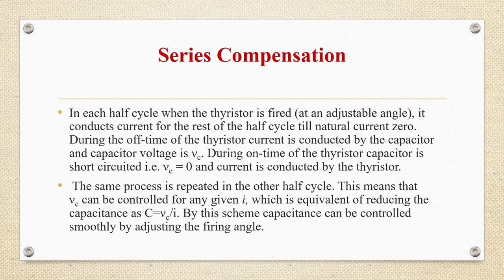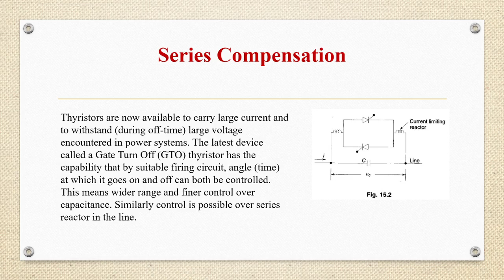Thyristors are now available to carry large current and to withstand the large voltage encountered in power systems. The latest device, called the gate turn-off thyristor (GTO), has the capability that by a suitable firing circuit, the angle at which it goes on and off can both be controlled. This means wider range and finer control over capacitance. Similarly, control is possible over a series reactor in the line. All the controlled and uncontrolled series compensators will require a protective arrangement. Protection can be provided externally either by a voltage arrestor or other voltage limiting device or an appropriate bypass switch arrangement. In no case should the voltage and current rating of the thyristor be exceeded.